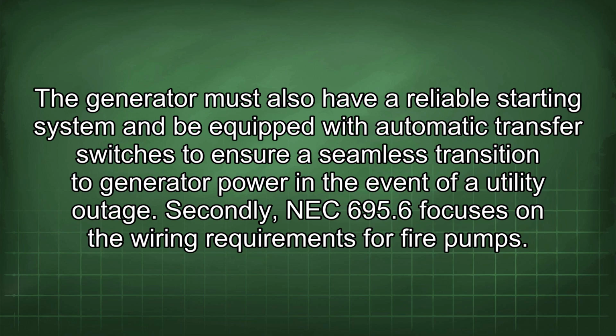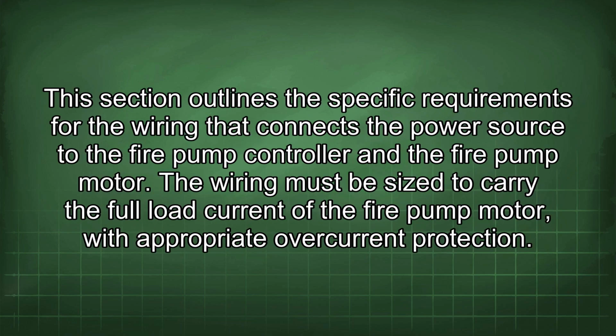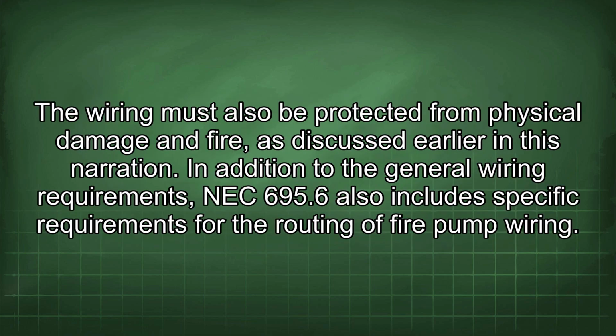Secondly, NEC 695.6 focuses on the wiring requirements for fire pumps. This section outlines the specific requirements for the wiring that connects the power source to the fire pump controller and the fire pump motor. The wiring must be sized to carry the full load current of the fire pump motor with appropriate overcurrent protection. The wiring must also be protected from physical damage and fire, as discussed earlier in this narration.